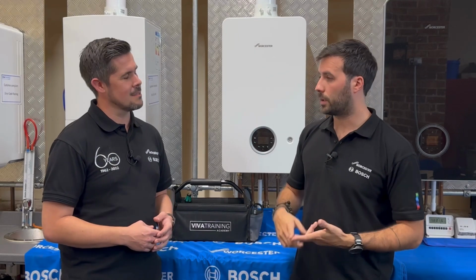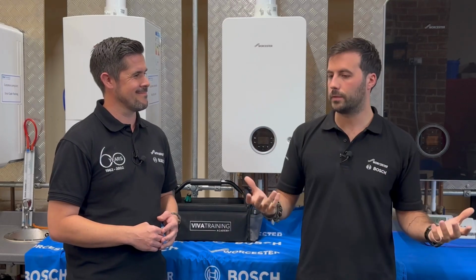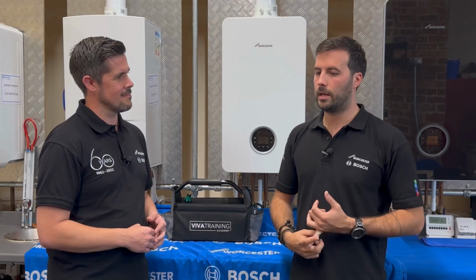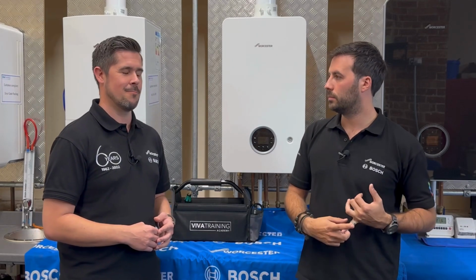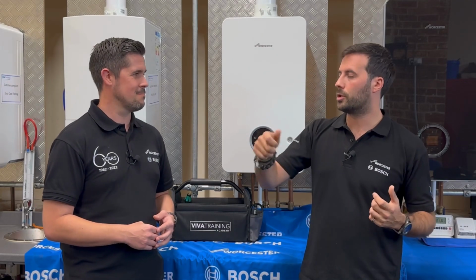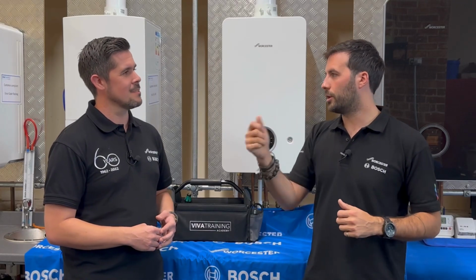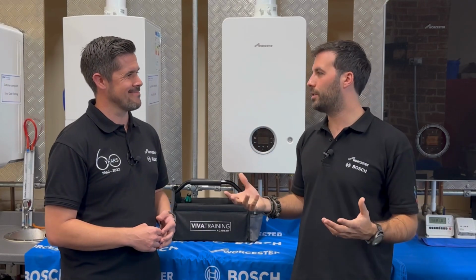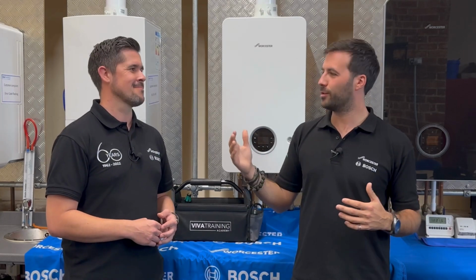So one way to do that is to design the system correctly, okay? But you can also do it from a retrofit kind of view. So you can install controls that will use lower flow temperatures at better times. Most people have got their boilers set at 70 degrees, let's say, 65 degrees. But you don't need that hot a flow temperature in the spring or autumn. So you could turn it down, and then come the winter time, you could turn it up. Well, that is the definition of weather comp. As the weather changes, the flow temperature changes.